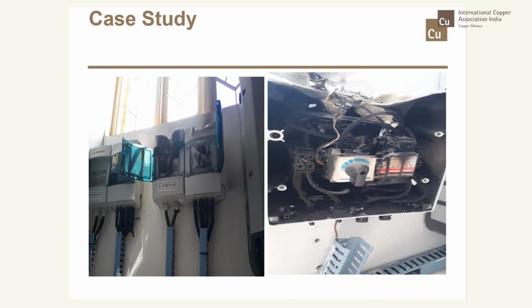We could not really identify the fault, but the most probable fault we have understood is possible loose wiring or loose termination on one of the isolators, and smoke started coming out. One of the persons occupying that building rushed in and isolated the DC fuse, which is not a good practice, because he isolated it under load condition, which caused an explosion, and the fire propagated. So the key learning here is that the loose connection could not be identified, which eventually led to large scale destruction, including the inverter.